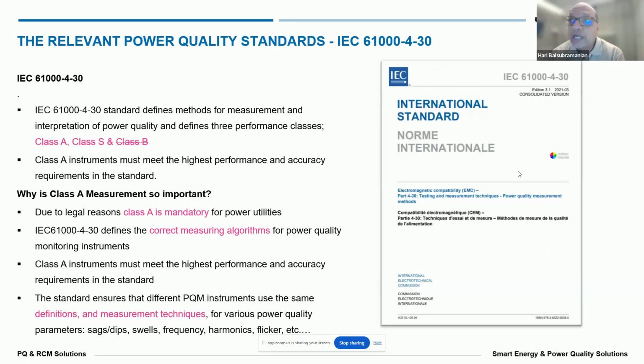Now, it is very important to know that there is a measuring standard for harmonic measurement, which means, how do we measure harmonics? Harmonic measurement is more of a calculation. As I said, it is a Fourier theorem. Different manufacturers could follow different calculation and sensing methodologies, so there may not be much uniformity. That is why the standard specifies two classes of devices, called class A and class S. Class A means it is a legally valid measurement methodology, which can stand in a court of law. Class S gives some room for the manufacturers to go their own way. So that's how class A and class S are defined in this particular standard.